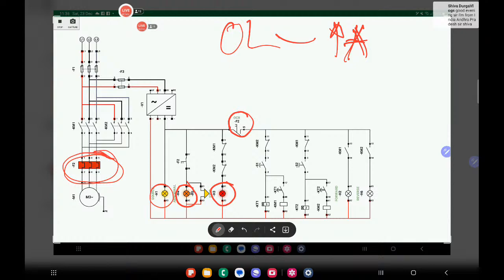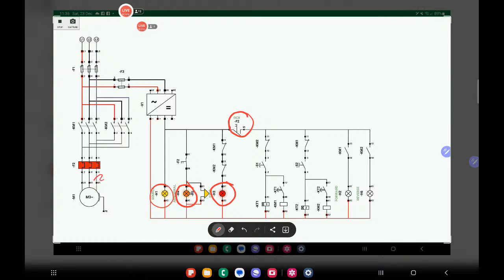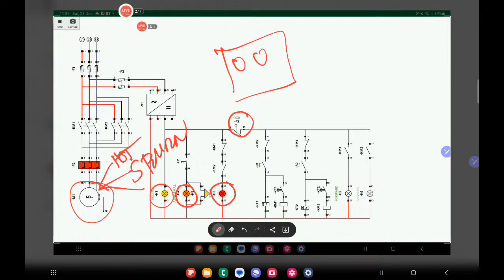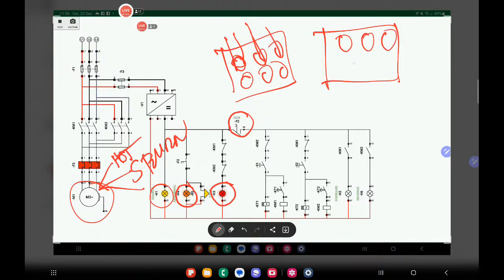Okay, the best way is to check first the condition of your electrical motor. Check if it is hot, if it smells burnt. Check the terminals if they are all intact and all the lugs are in good condition, right? Do an insulation resistance test. So continuity test, and then do a line to ground test on the electrical motor so that you will know, no?